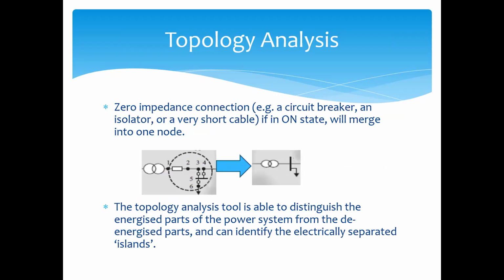For example, a zero impedance connection, a circuit breaker, an isolator, or a very short cable, when in ON state, will merge into one node. You can see here transformer, short cable, circuit breakers, isolators, all these things come together and make one node. So the transformer is there, this bus bar is there, and the load is there. All these things become one node. The topology analysis tool is able to distinguish the energized part of the power system from the de-energized part and can identify electrically separated islands.